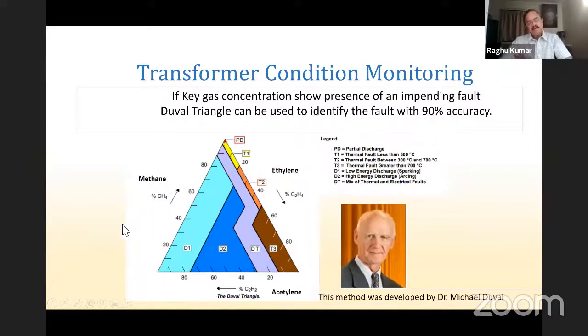There is one disadvantage for this method. You have to be initially sure there is a fault present. Otherwise, the Duval triangle does not have a location which says no fault. Every point in this triangle is a fault. So you have to be initially sure that there is a fault present to use the Duval triangle.